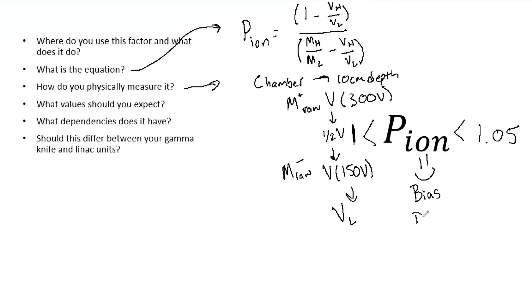And then finally we also have our dose rate. The dose rate changes the density of the charge cloud within the chamber, and that is going to alter our P ion.